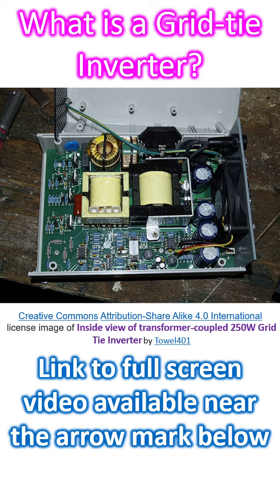When the grid tie inverter is properly configured, it enables the building to use an alternate power system such as solar panels without extensive rewiring and without storage batteries. When there is a deficit in production, power is drawn from the grid, while the excess production, if any, is transferred to the grid.